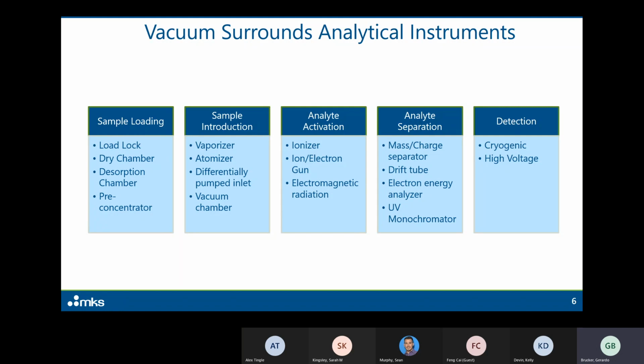And that could be ionization, like in a mass spectrometer, where we have to hit the sample with electrons, or maybe with UV or VUV photons, or even ions from an ion or an electron gun, in which case I need vacuum to make sure that I don't lose those electrons or those ions to neutral collisions, right? Collisions between electrons and neutrals or ions and neutrals. So vacuum is essential for all these. And even if what I'm doing is just bringing in photons to activate the sample, I still need vacuum in those cases.